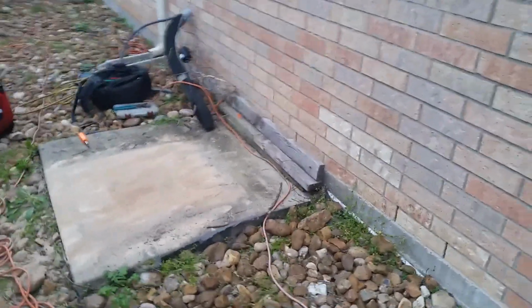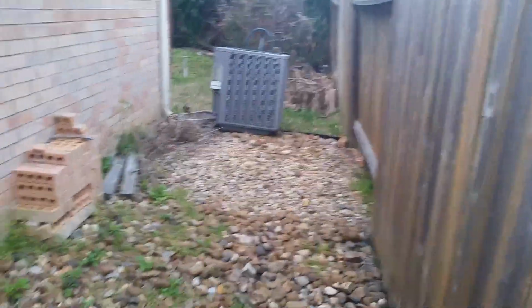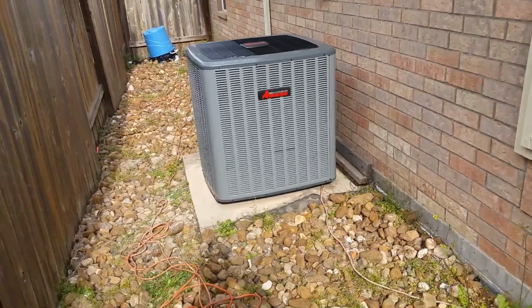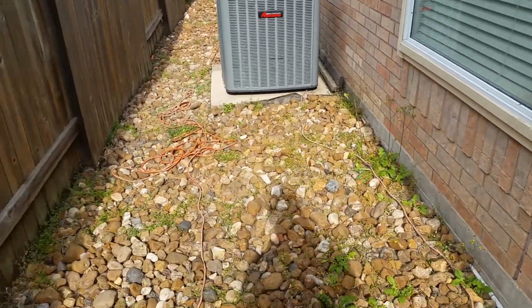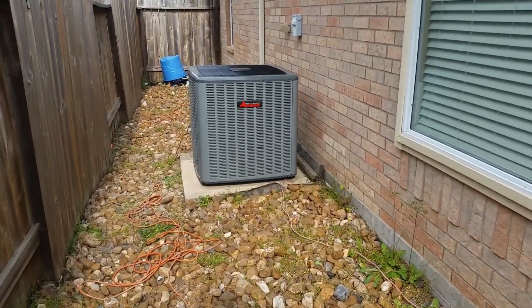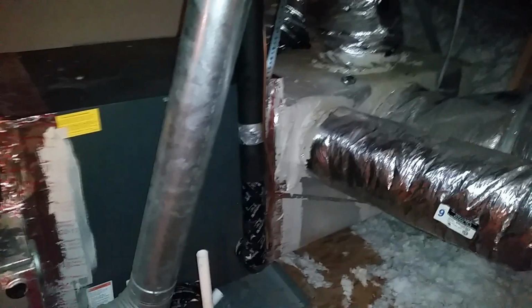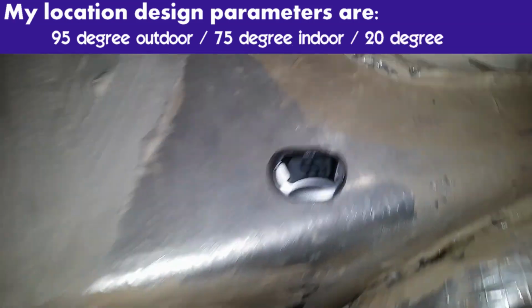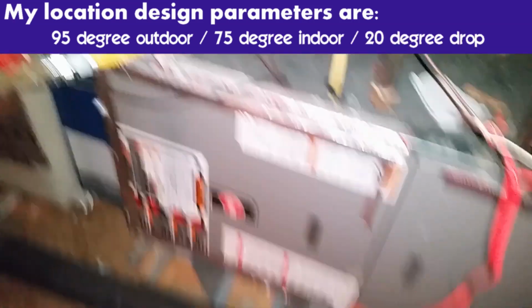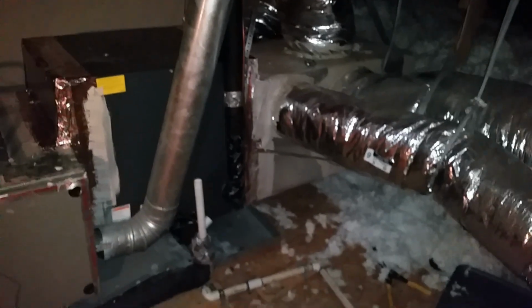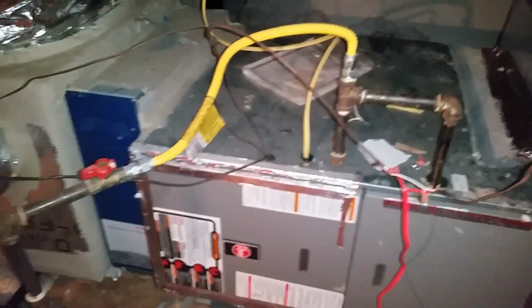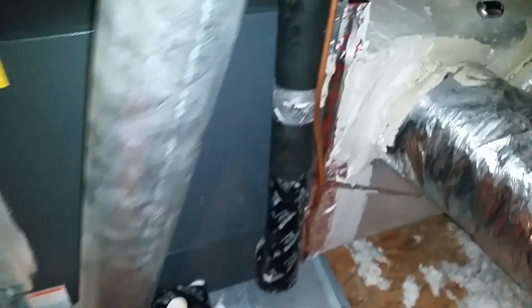Here I am again showing the removal of the outdoor unit. And it's kind of a hard way to get it out because of this rock garden they got going on. That's the new unit set. And by this time it's already installed. It wasn't running during this time, but here it is running in the attic. This is the new coil installed, all the piping hooked back up, ductwork hooked back up. You see a 55-degree temperature drop. It was a 75-degree indoor temp, so it had right at 20 degrees temperature drop across the coil, which is always a good figure to have.